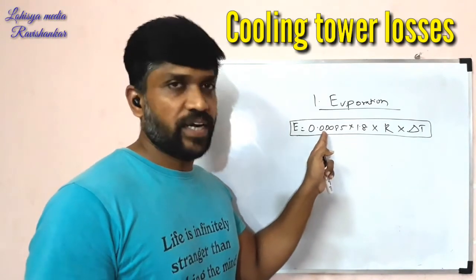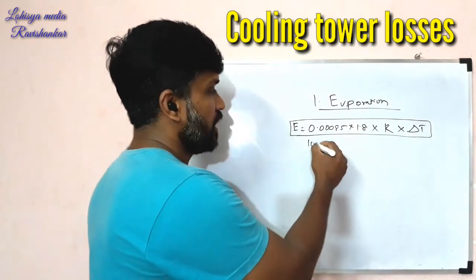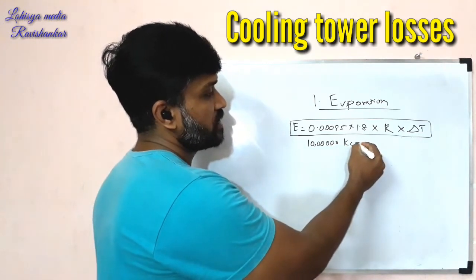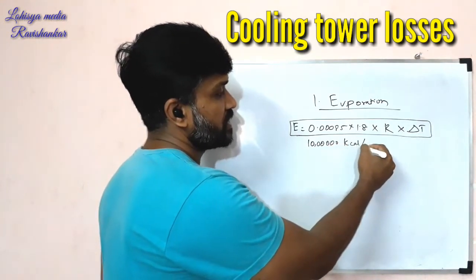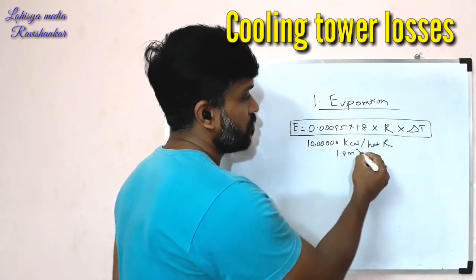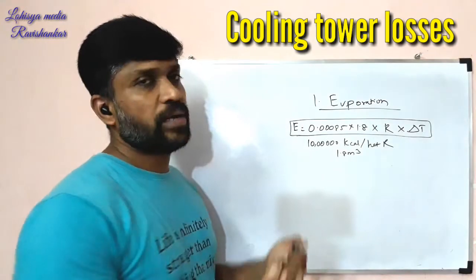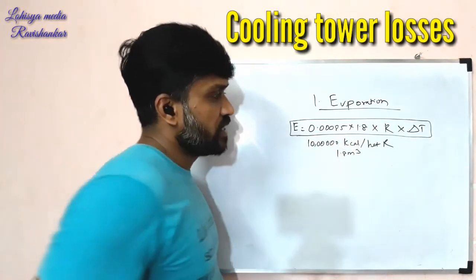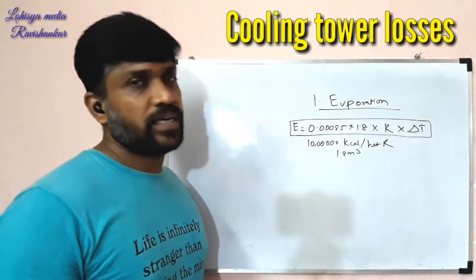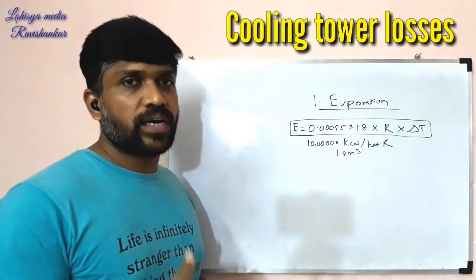This formula is directly for evaporation. Just give the correction factor: 1.8 — for every 10 lakh kilocalories of heat rejection, 1.8 m³ of water will be used in evaporation. Evaporation equals 10 lakh kilocalories heat rejection per 1.8 m³ of water evaporation loss.